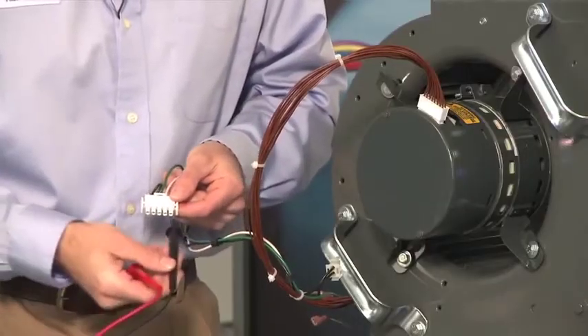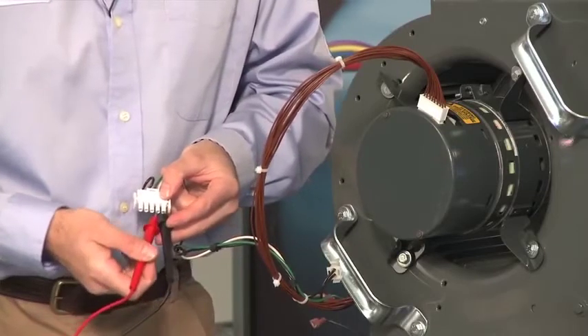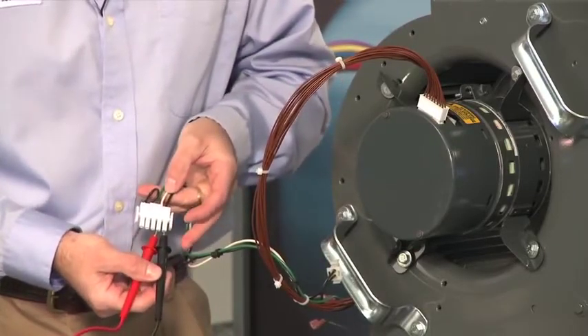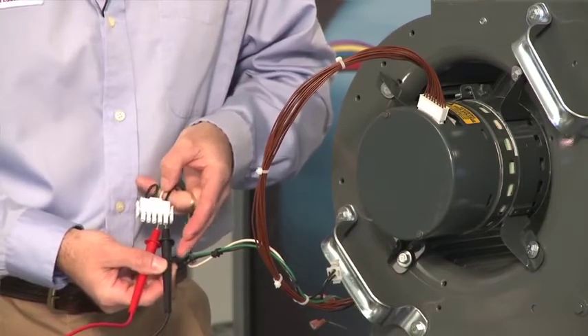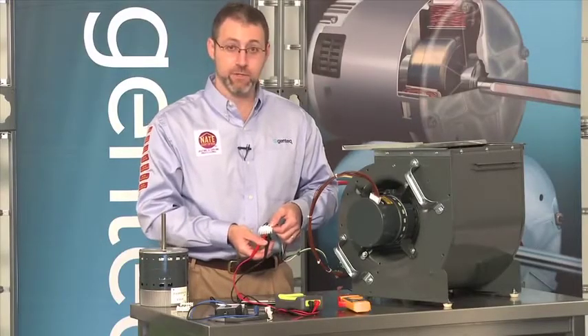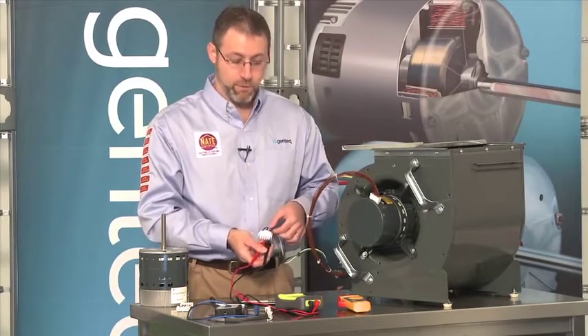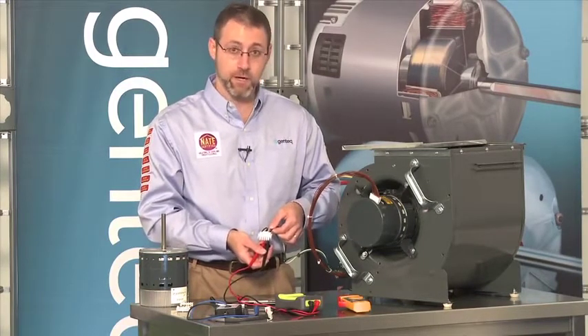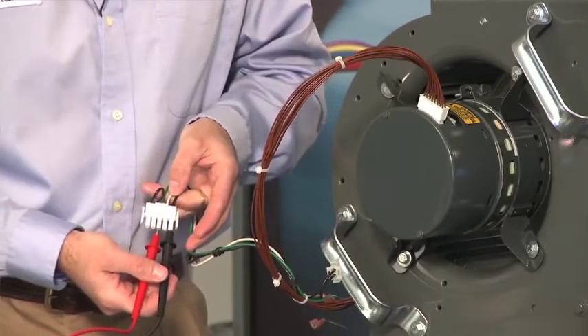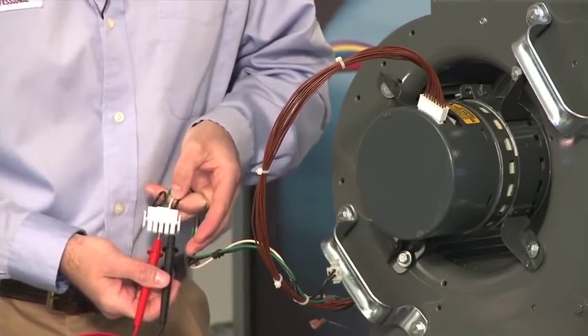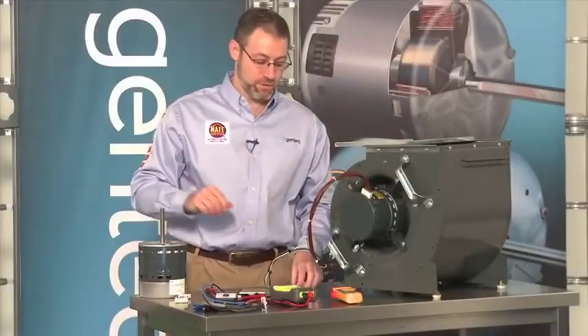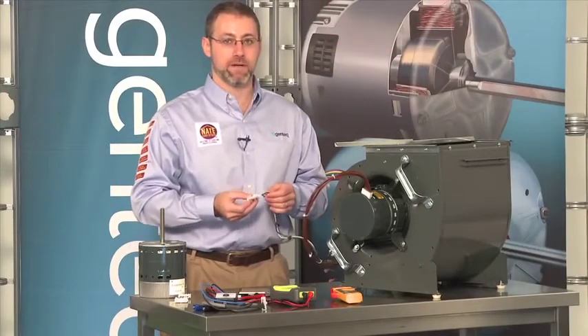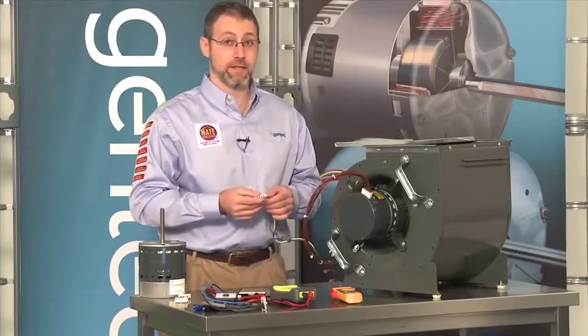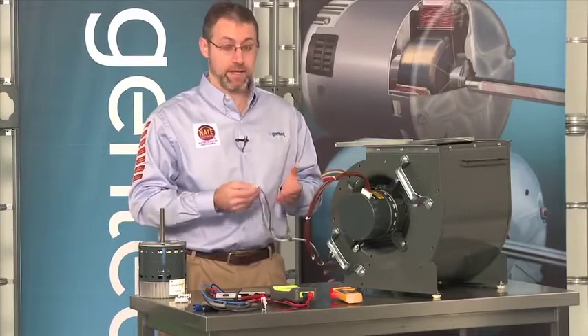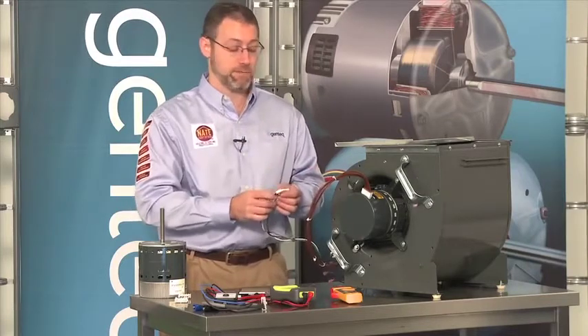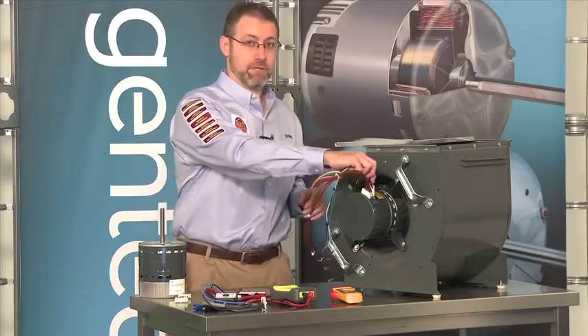And I'm going to put my connections on the black and the white wire, which in the case of a 120 volt system, I would see 120 volts between my black and my white wire. In the case of a 240 volt system, I would see 240 volts between my black and my white wire. And then I would also want to check between the black and the ground to make sure that I have a good ground as well. So we've already diagnosed that we have power to our 5-pin connector. Let's just assume that we didn't have power there and we repaired that. That may be the only problem and we're ready to put it back on the motor. We would then of course turn the power off and plug it back in.